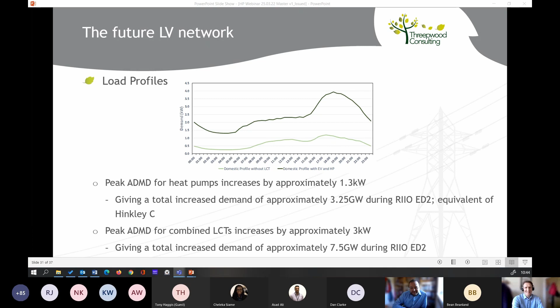A big thing that DNOs are looking to move to is the distribution system operator environment, and ENA's Open Networks project is leading on this, not just within the UK but also globally. A large part of that is called flexibility services, where the DNOs are looking to manage the networks via flexibility, shifting that peak load and demand around across the 24-hour period, rather than just reinforcing or updating cables when the limit is reached.